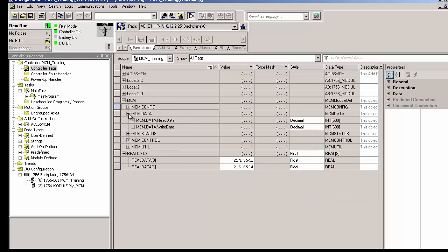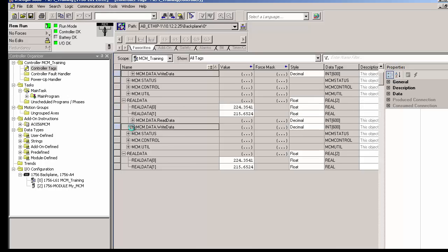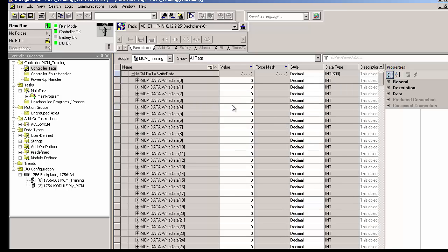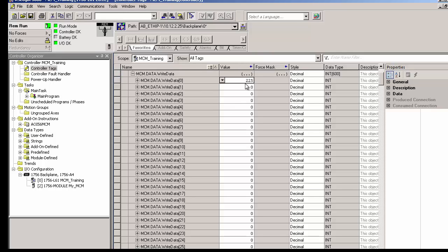Now we can write some data to the power monitor to set a limit and reset the minimum and maximum values for phase A voltage. So in our first command, we want to set the limit. We'll drill down to MCM.data.writeData 0, which is where we specified we'd be writing from in the command. I'll enter a value of 225 to set the limit in the monitor to 225 volts on phase A. Now, if it goes over this limit, the monitor will send an alert.